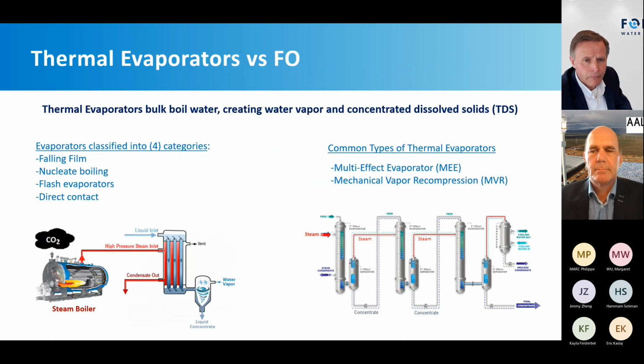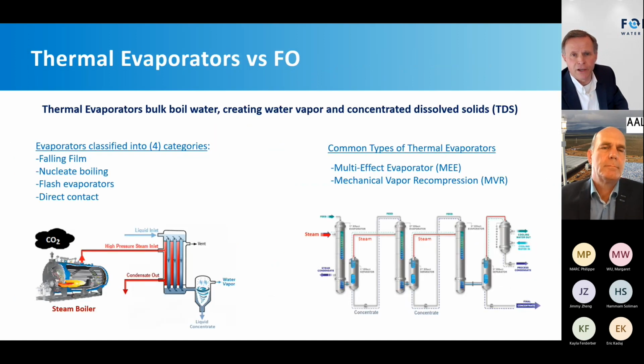Getting into conventional versus FO on the energy side - conventional is a thermal evaporator or bulk boiler, where I take the entire fluid in and hit it with high pressure, high temperature, and distill water off like a kettle. It's very energy intensive, has a large footprint, and because of the complexities and aggressiveness of the brines as you concentrate it up, these are built with very unique or exotic metals such as Hastelloy, titanium, and are very expensive.